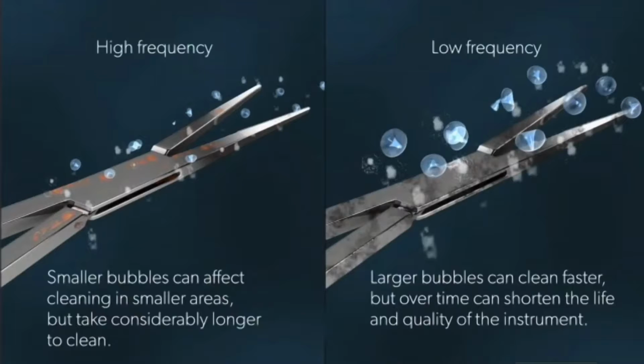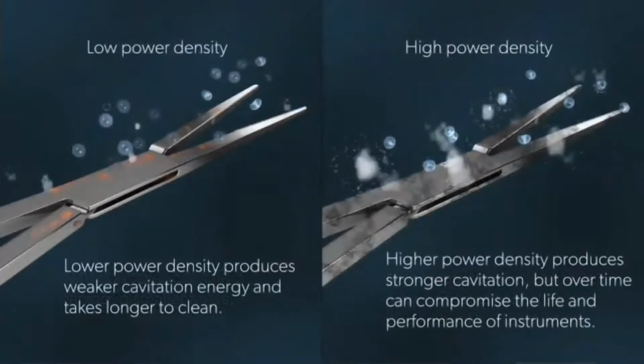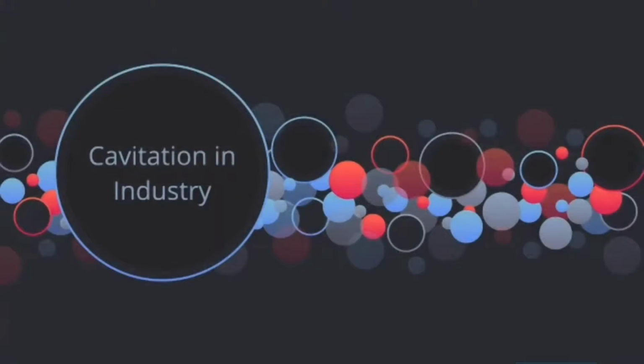We know that. But if you have your low frequency cleaning aspects with larger bubbles, over time your instruments can take a beating. Let me continue to explain this a little further with you. First, about differing powers. Lower power density, if you have less power, you're going to be able to produce less work, so it could take longer to clean. But if you have really intense power, higher power density produces stronger cavitation, and over time can also compromise the life of the performance of your instruments, as depicted on the right side, where pitting can form. Let me demonstrate this a little further.